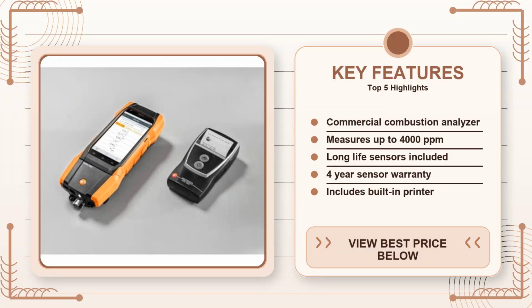That stability matters because a drifting sensor can give you a false sense of safety, especially when you're measuring low CO levels. The 4-year sensor warranty isn't just a nice guarantee, it tells you Testo expects the sensor to hold up under typical commercial use, which usually means exposure to temperature spikes and occasional moisture. In real-world terms, you'll spend less time recalibrating and more time actually diagnosing burners.